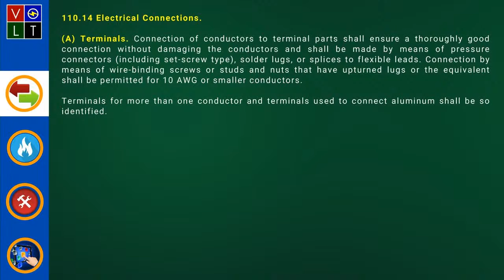This is a funny little myth because it comes from a lot of home inspectors failing installs for having 2 hot conductors, or 2 ungrounded conductors, underneath one breaker. There are breakers listed for that, most notably the Square Ds, I don't think there's any that aren't. But in all actuality, you'd have to have circuits that are, say, 10 amp non-continuous loads or whatever, not just 2 20 amp loads on that 20 amp breaker. You'd have to have a load the breaker could actually handle, if you're going to do that.